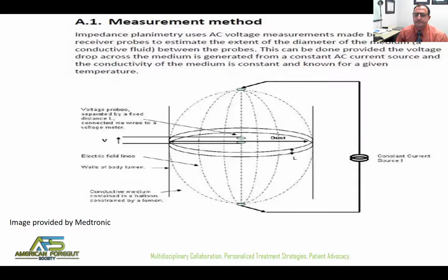Thus, the cross-sectional area can be calculated by measuring the voltage across paired electrodes spaced at a known distance as the balloon is filled with a fluid of known conductivity, in the case of FLIP, saline, while excitation electrodes at the other end of the balloon emit a continuous low electrical current. Finally, assuming a circular lumen, the cross-sectional area can be converted to a diameter to aid in clinical interpretation and application. And finally, by applying Laplace's law, the esophageal lumen distensibility can be calculated from the cross-sectional area and the balloon pressure data.